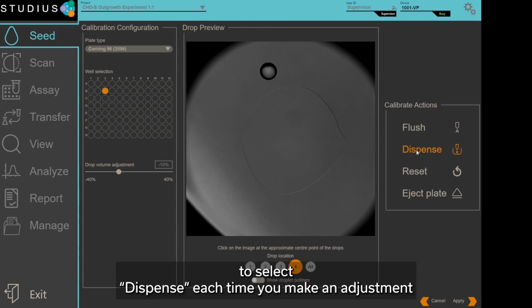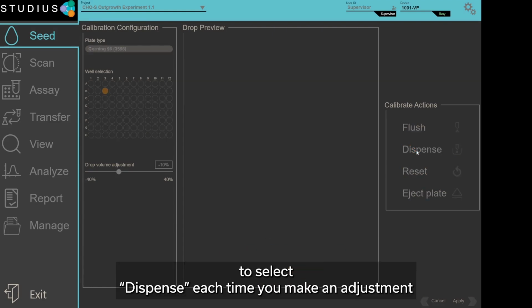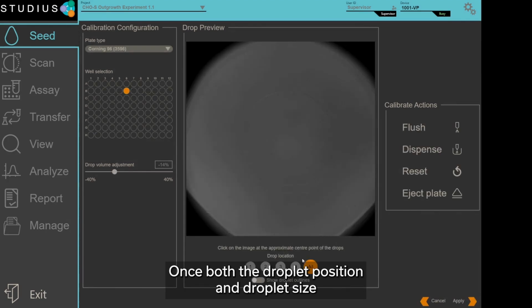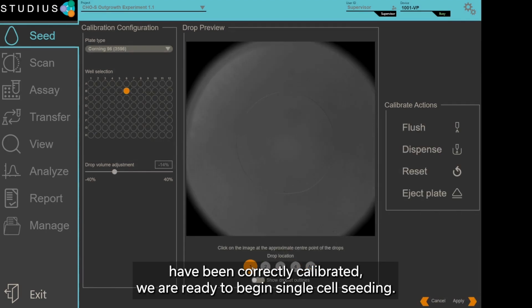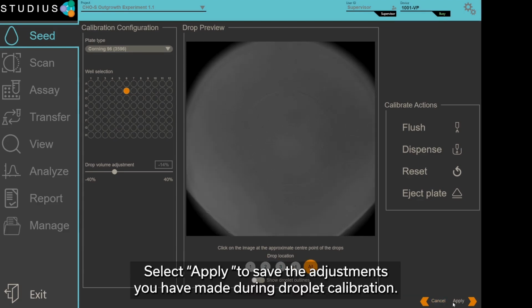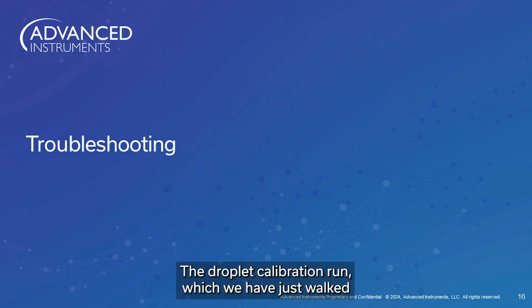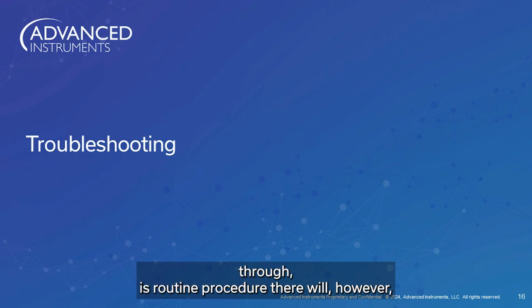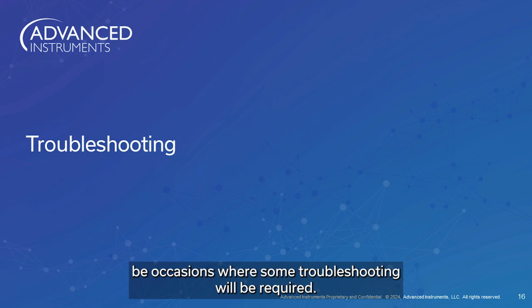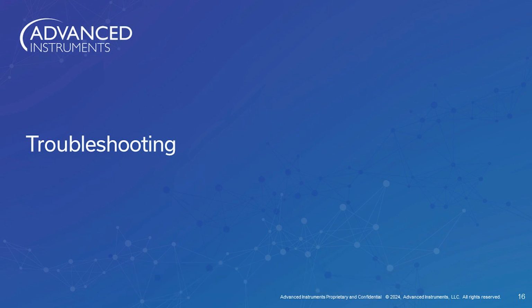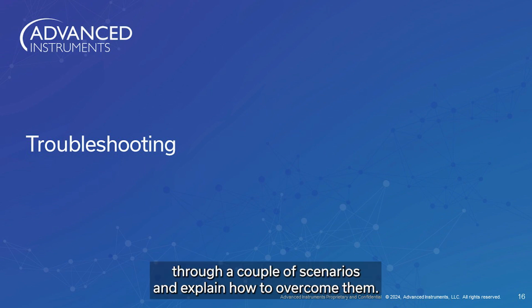Make sure to select Dispense each time you make an adjustment so that you can monitor the changes that you are making. Once both the droplet position and droplet size have been correctly calibrated, we are ready to begin single cell seeding. Select Apply to save the adjustments you have made during droplet calibration. The droplet calibration run, which we have just walked through, is routine procedure. There will, however, be occasions where some troubleshooting will be required. I'm now going to walk you through a couple of scenarios and explain how to overcome them.